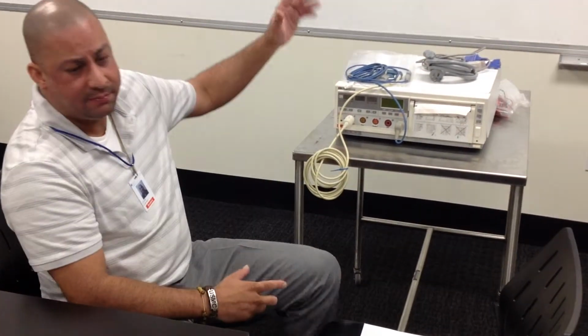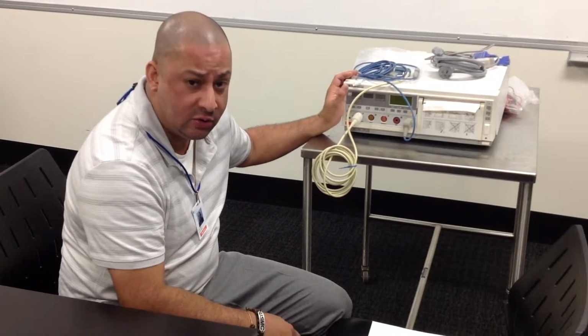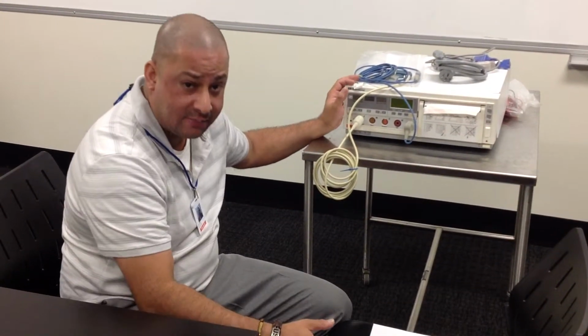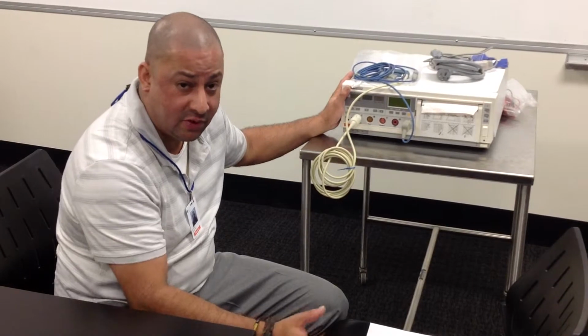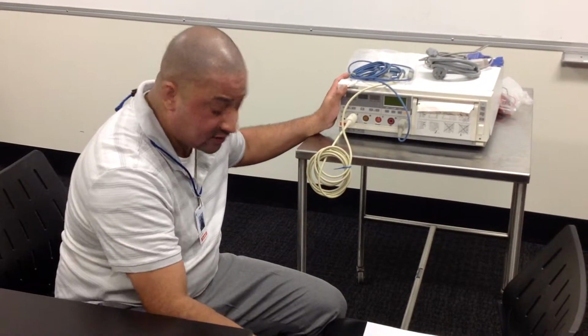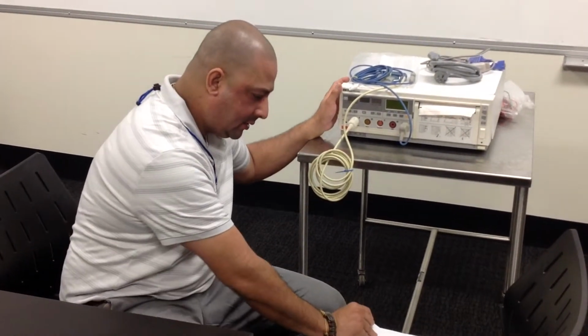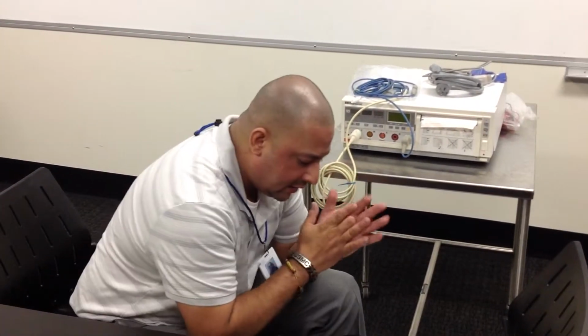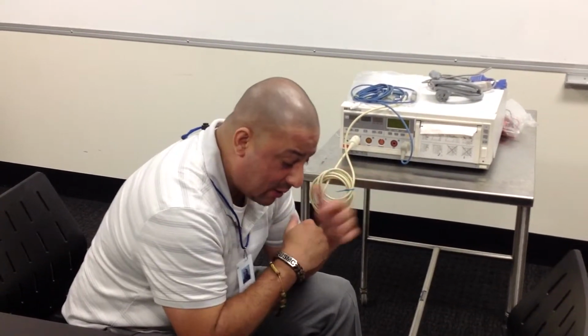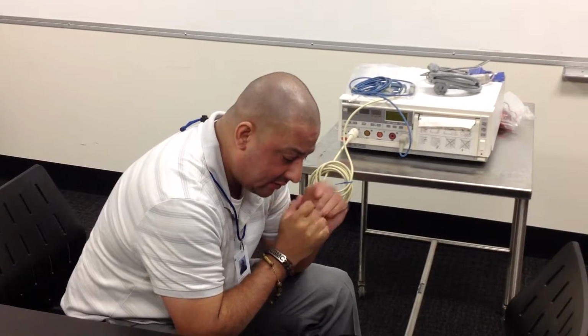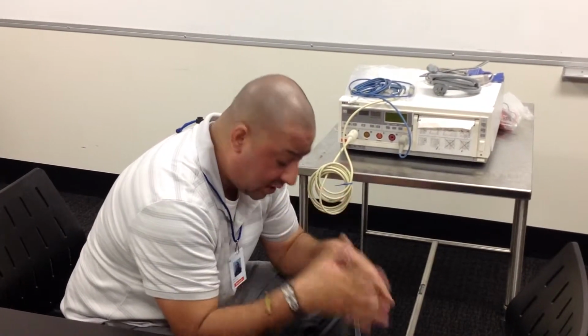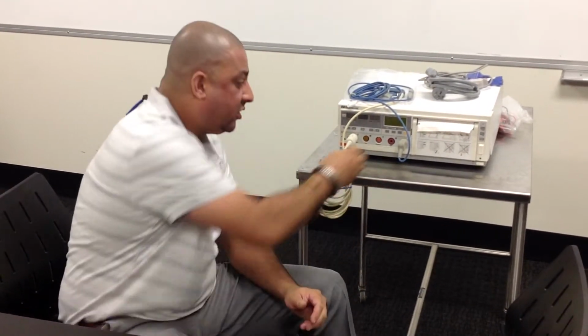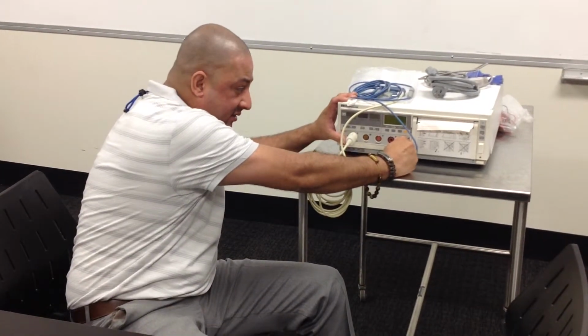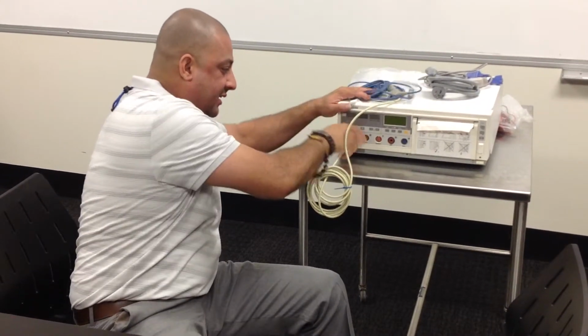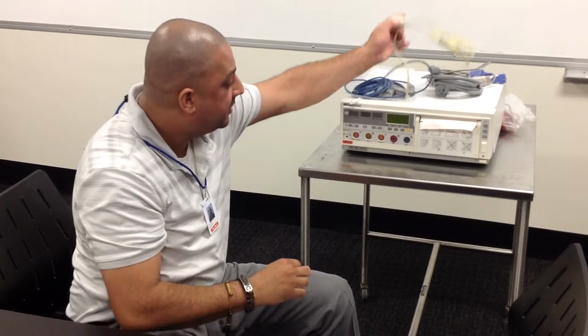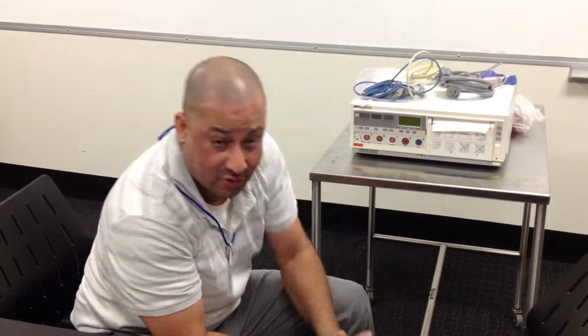Like most devices, before you use it, it is recommended that you do a pre-operative check to make sure all the systems are up and running before you actually connect it to the patient. So having said that, we're going to move forward. What I'm going to talk about next is what's called the NIBP calibration. According to this manual, the first thing we're going to do is ensure all the transducers, which are these things, are disconnected. And of course, we do not want them connected to the patient while we're performing the calibration.